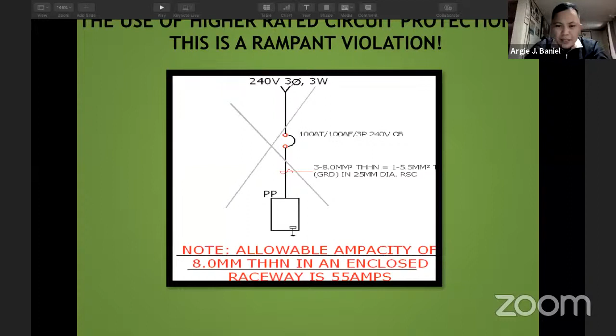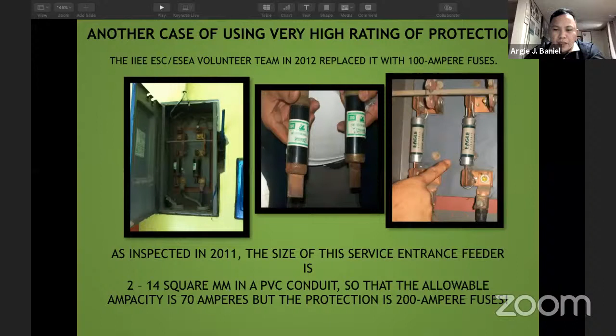As inspected in 2011, the size of this service entrance feeder is 14 square millimeter in a PVC conduit, so the allowable ampacity is 70 amperes, but the protection is a 200 ampere fuse. This is similar to what we discussed earlier—the 14 square millimeter wire still won't be protected from overload because the fuse installed, a 200 ampere fuse, has a much higher rating.